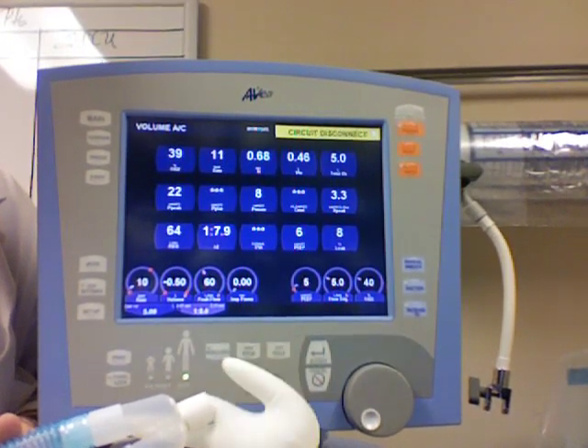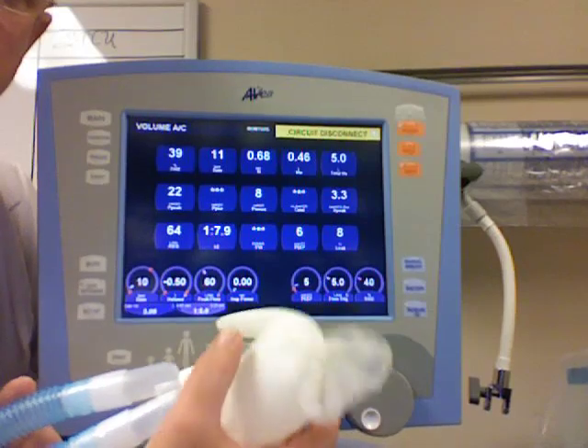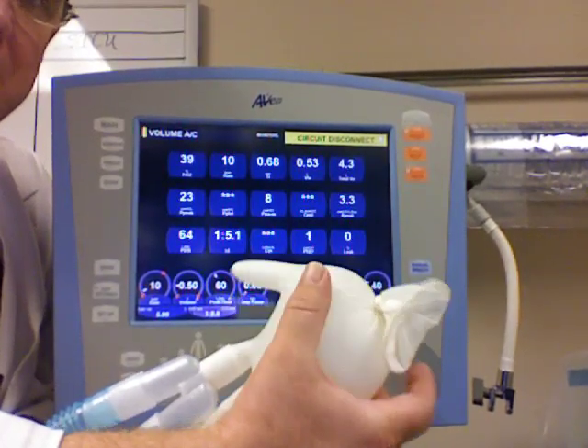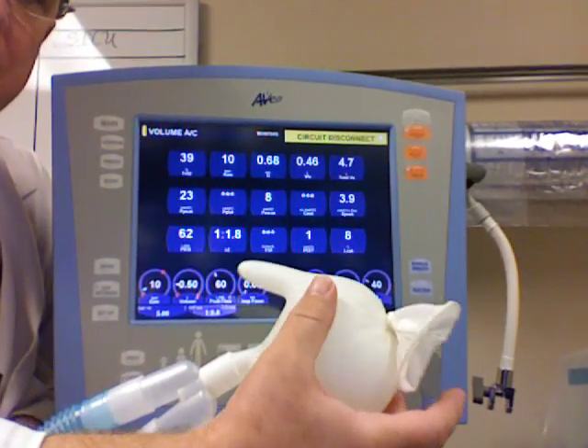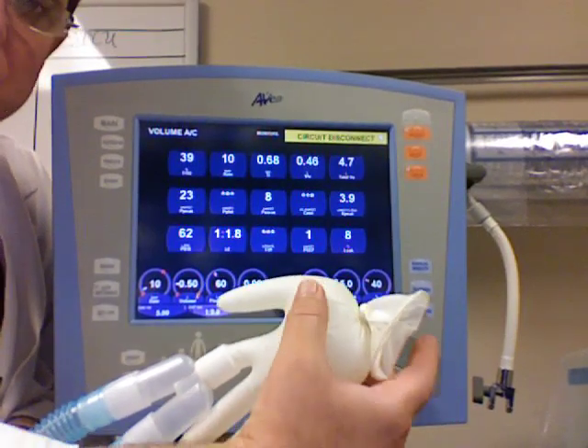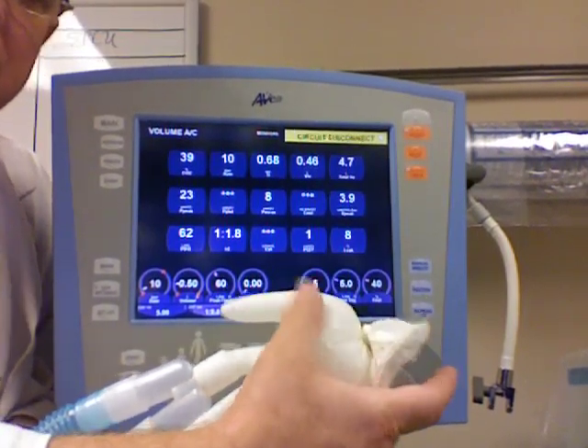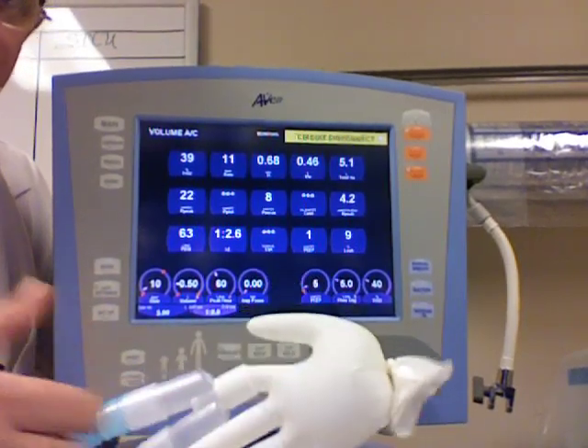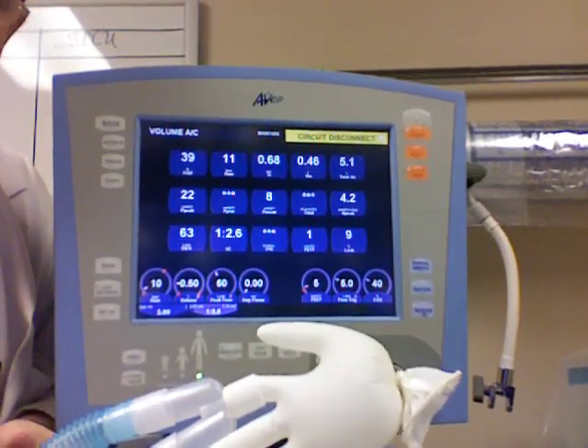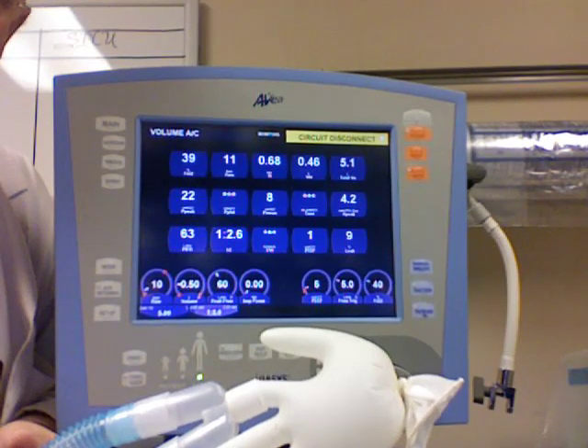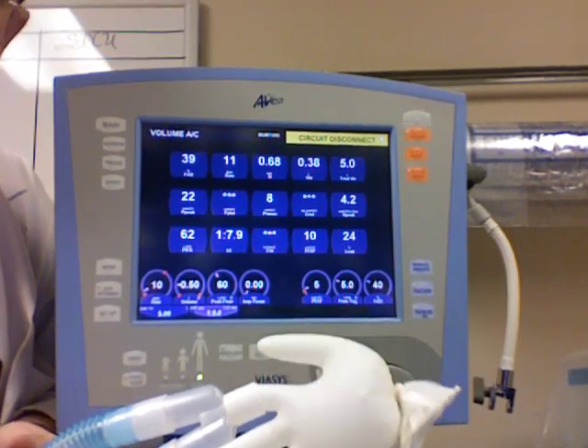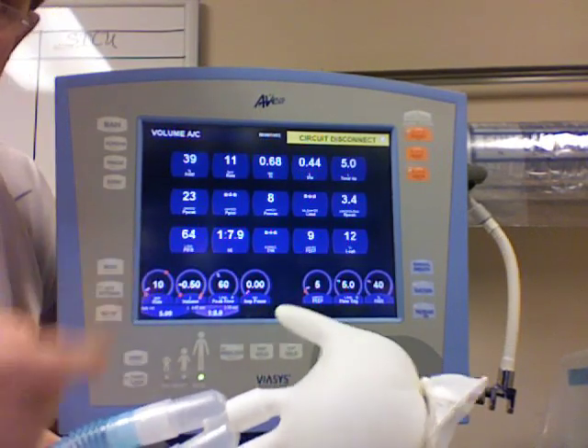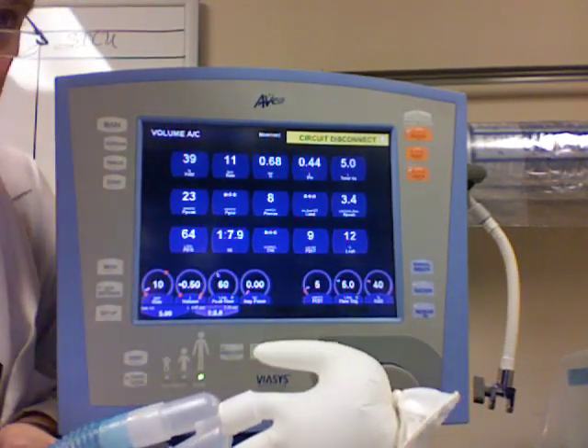What happens if the patient wants an additional breath? Here's the assist breath — the patient makes an effort. How does the ventilator know the patient is making effort? When I squeeze it, it delivers the tidal volume to them. So basically in assist control, every breath has a termination criteria of 60 liters per minute, whether the patient starts the breath or whether the machine says it's time for one because of the rate. That's the nature of assist control.